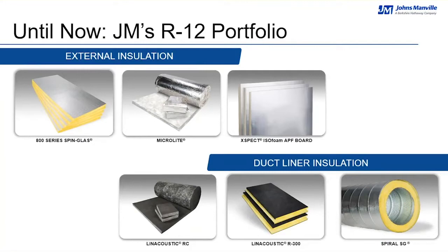For external duct insulation, JM's 3-inch 800 series spin glass, JM's 4.4-inch Microlite duct wrap, and JM's 2-inch Xspect ISOfoam APF board all carry an R value of 12 or greater.